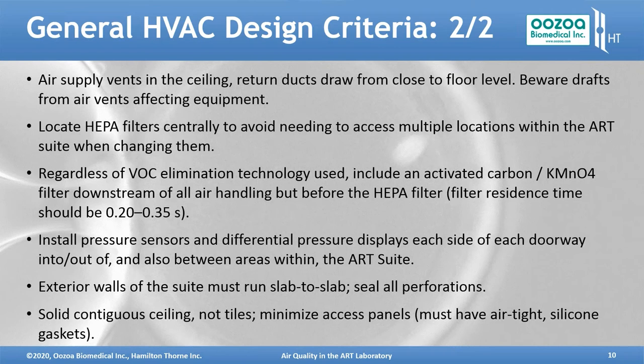You should have pressure sensors and differential pressure displays each side of each doorway going into or out of the ART suite and also between areas within the ART suite. The exterior walls of the suite must run slab to slab. Seal all the perforations. You're creating a sealed box. And that means that the ceiling needs to be solid, contiguous ceilings, so not ceiling tiles, and then even minimize access panels. And the access panels that must be there for whatever reason need to have airtight silicone gaskets to stop the air leakage.